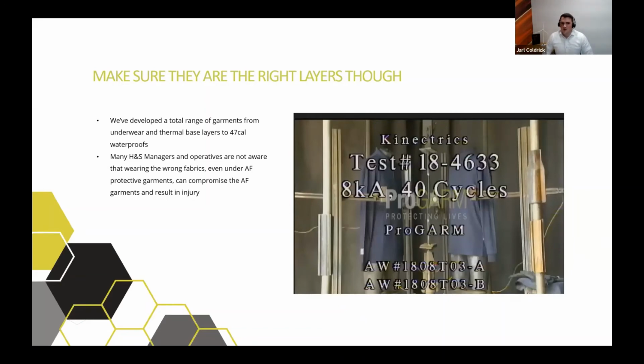It's also important to make sure they are the right layers. Often we see individuals wearing their arc flash clothing but compromising by wearing an undergarment that doesn't necessarily meet the standards. In this video, we tested two arc flash polo shirts to see what would happen to the inner layer. On the left mannequin, you've got an arc flash polo shirt with an FR and arc base layer. On the right mannequin, you've got an arc flash polo shirt that's okay on the exterior, but underneath is 100% cotton. Let's watch what happens.